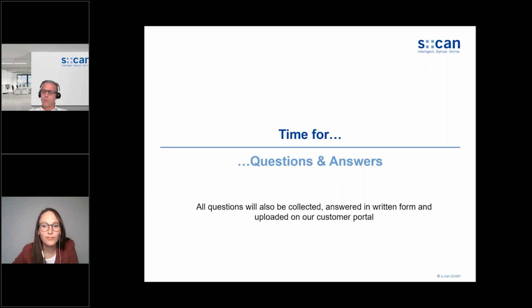And furthermore, the nitrogen removal in the biological treatment has to be monitored in situ. It makes no sense to take a lab sample, not only due to time, but you have to be really inside the reactor to know what is going on. You cannot even pump the water out of the basin and put it to a measuring station operating in bypass. This makes by far no sense. So these two points are for me the reasons why the biological treatment plant is by far the most important one.